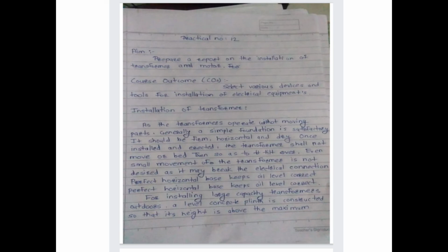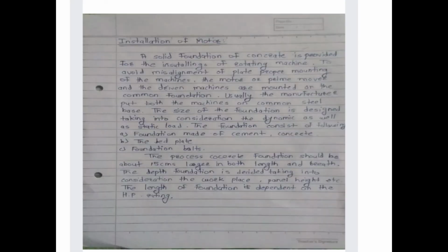A perfect horizontal base keeps the oil level correct. For installation of a large capacity transformer outdoors, a level concrete plinth is constructed so that its height is above the maximum expected flood water level of the site. Then the installation of motor. A solid foundation of concrete is provided for the installation of rotating machines to avoid misalignment of plate and for proper mounting of the machine. The motor and prime mover have a common foundation.